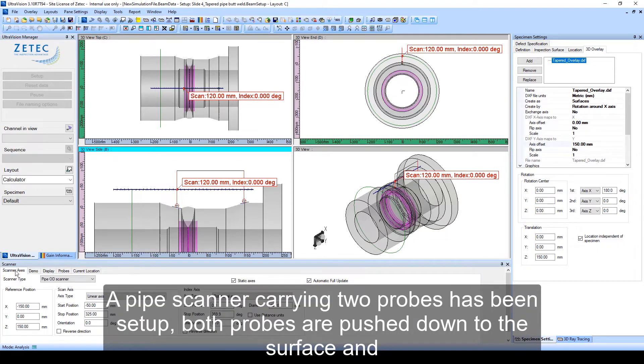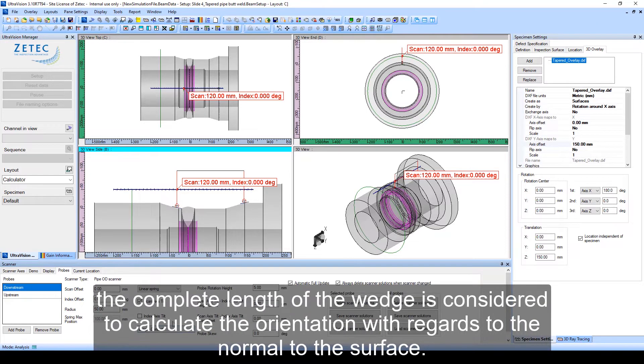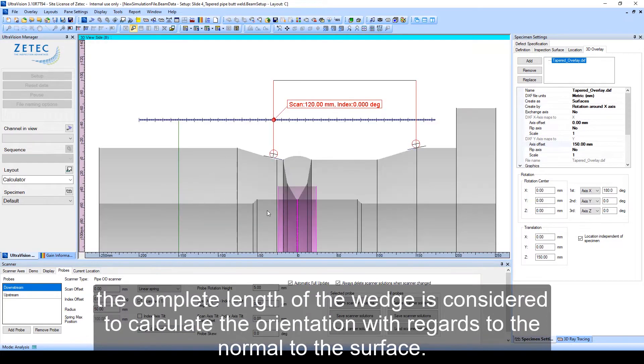A pipe scanner carrying two probes has been set up. Both probes are pushed down to the surface, and the complete length of the wedge is considered to calculate the orientation with regards to the normal to the surface.